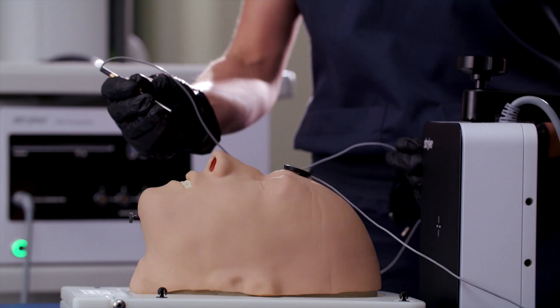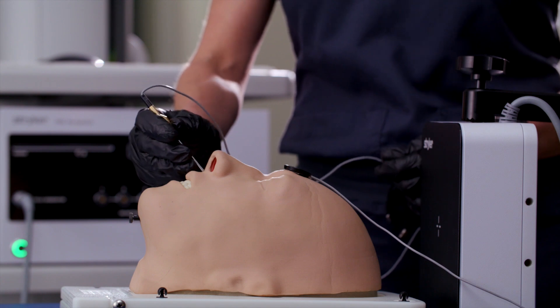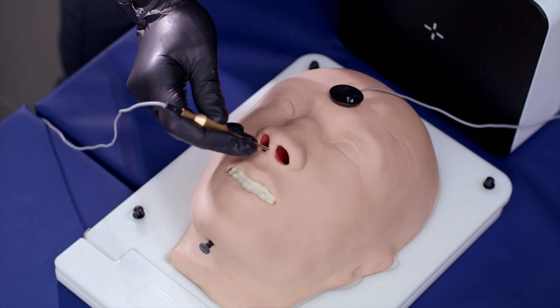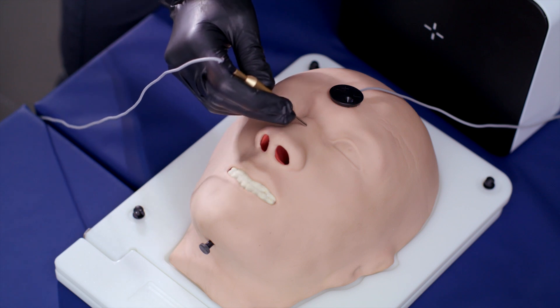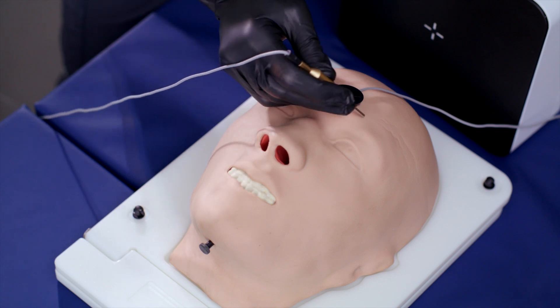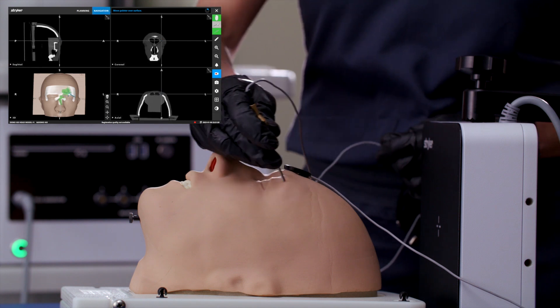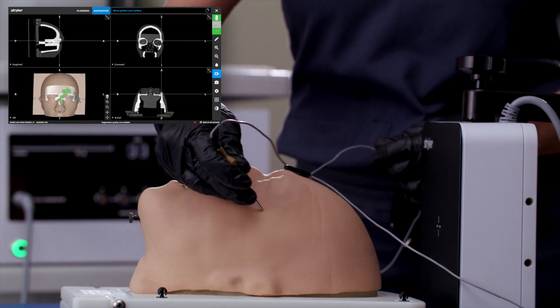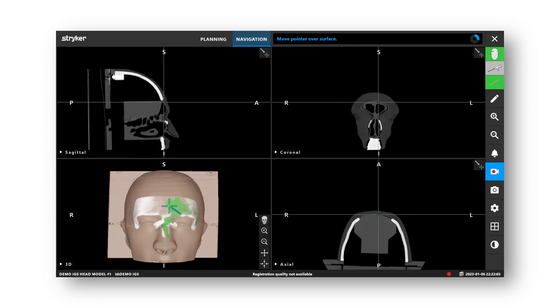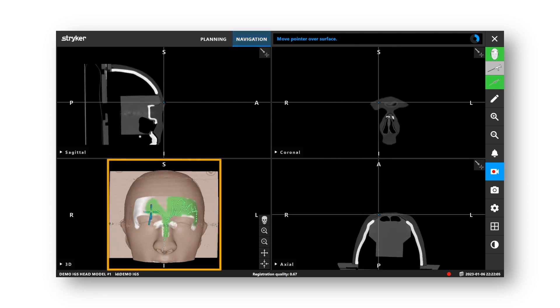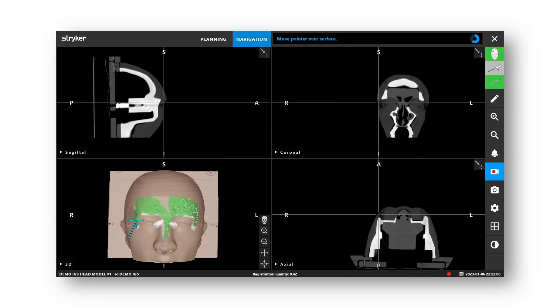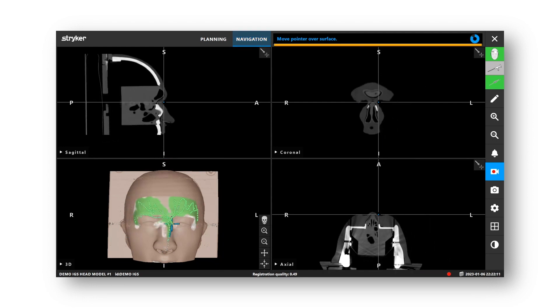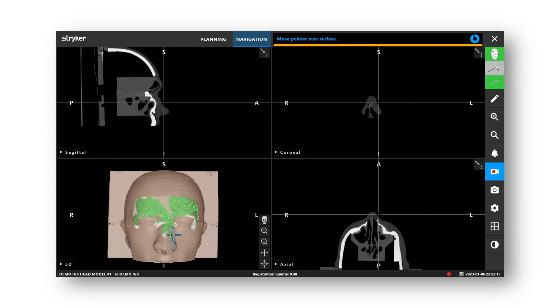Hold marker at point one until you hear the audible beep and without lifting off the patient's skin, trace until you've hit point two and you will hear a second audible beep. Continue moving the pointer over the surface in wide curves with a light feather touch. The more bony structures that are traced, the more accurate the registration. The white color in the 3D view highlights the most suitable areas for tracing. The progress wheel in the message bar indicates the progress of the registration.